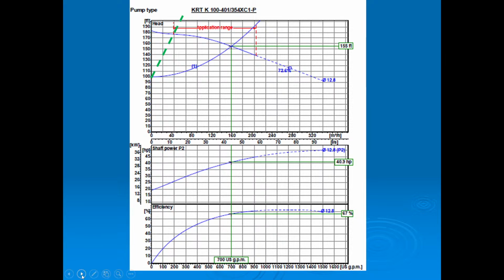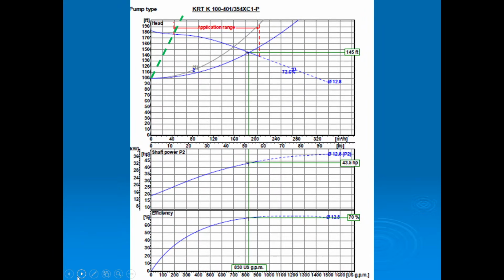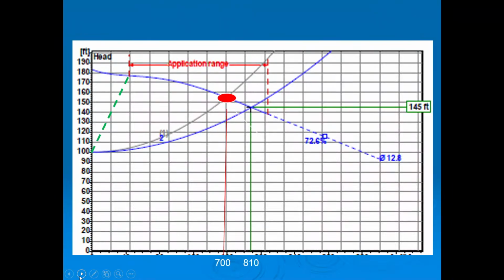So when we do our C factor, when we do our pump station curve on our computer, we look at two different C factors. We come up and say, okay, the left one is the specified one. That's typically what the engineer is going to give us as a supplier. Hey, I want you to do 700 gallons a minute at 150 foot head. Perfect. So we do that.